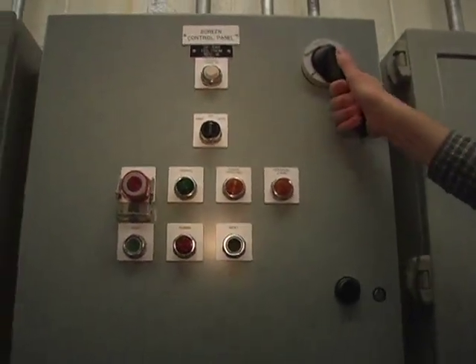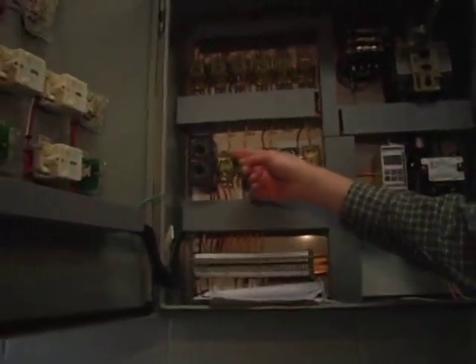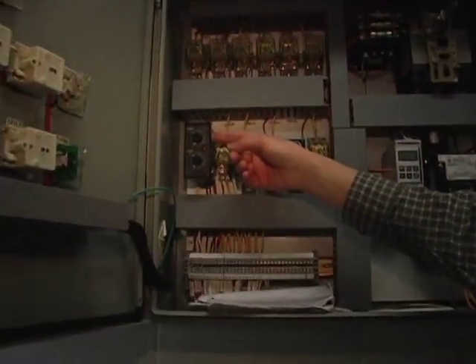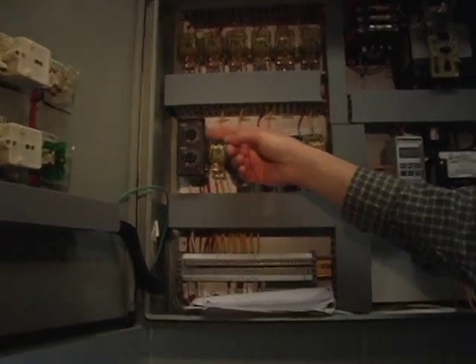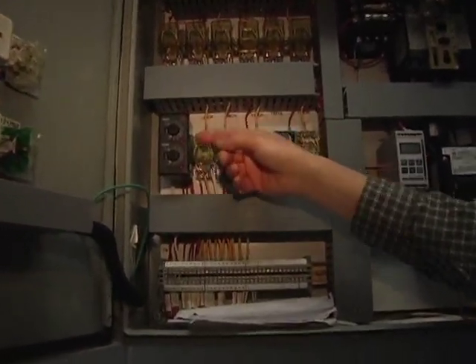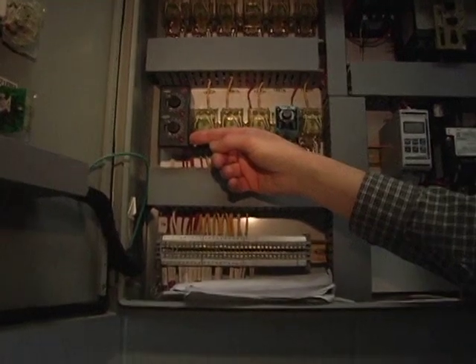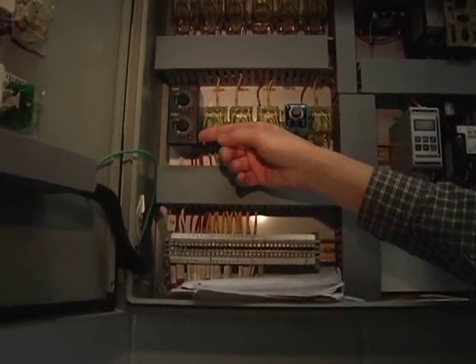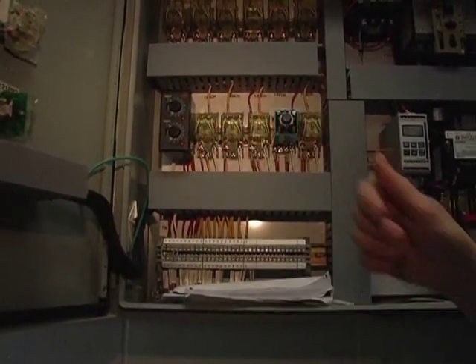Within the panel itself, these are the timers used to control the bar screen locally. There's the off timer, which is currently set for 10 minutes, and the on timer, which is currently set for 5 minutes, which will operate the screen on a time basis.